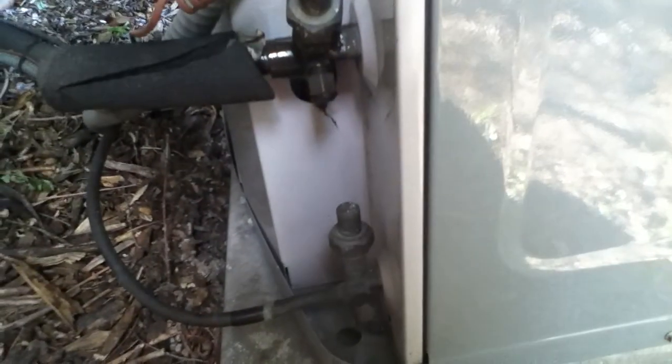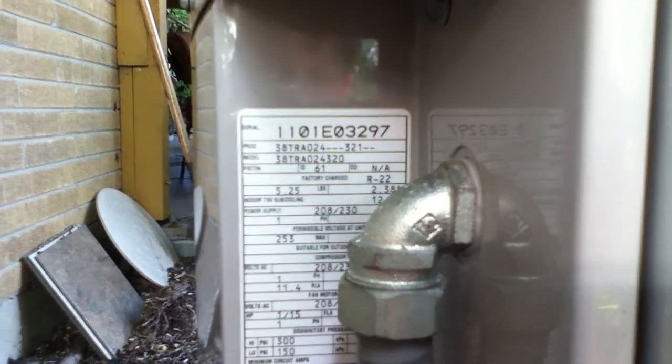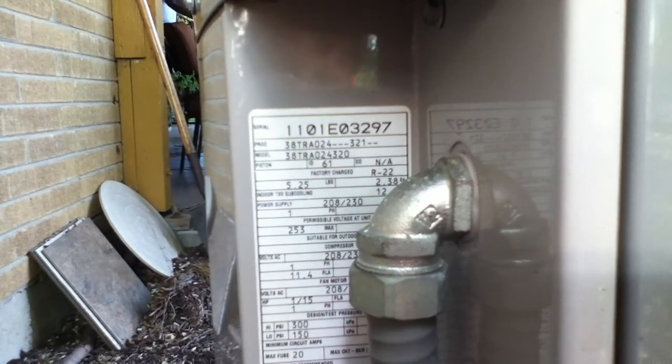The liquid line is just about outdoor air temperature so it's charged perfectly. And it has as good a sub-cooling as I can tell, because I don't have the charts. The serial number is 1101-E03-297 and the model number is 38-TRA-024-320. So it's from the 11th week of 2001 and it's a 2-ton unit.